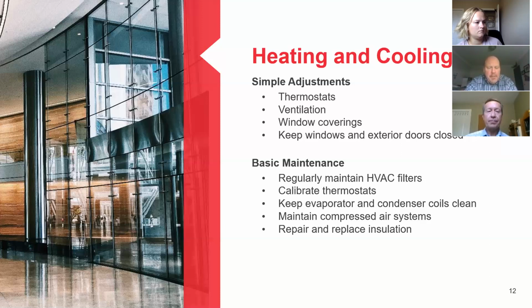The basic maintenance, again, I go back to the filters, making sure the filters are clean and new, so that equipment doesn't have to work harder. Calibrate all your thermostats. Make sure all your set points are where you want them to be, and take control of those thermostats away from people. It's typical for people to turn thermostats up or down when not required. So just make sure that you have control over that. Keep all your condenser and evaporator coils clean. Again, plugged coils make equipment work harder. And if you do have a compressed air system in your facility, make sure there are no leaks. A leak in a compressed air system makes the motors work harder and run more. So make sure that all leaks are repaired and that your compressors don't have to work as hard. And again, I go back to repair and replace all the insulation. Make sure that the heating and cooling is kept where it needs to be and it's not lost due to faulty insulation. Next slide, please.